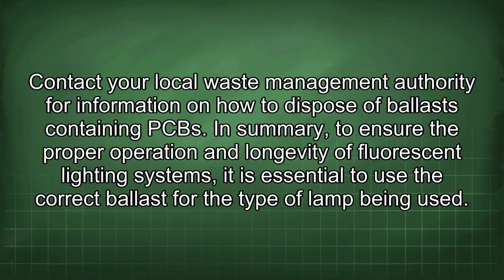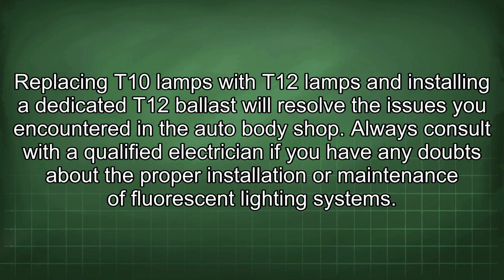In summary, to ensure the proper operation and longevity of fluorescent lighting systems, it is essential to use the correct ballast for the type of lamp being used. Replacing T10 lamps with T12 lamps and installing a dedicated T12 ballast will resolve the issues you encountered in the auto body shop.